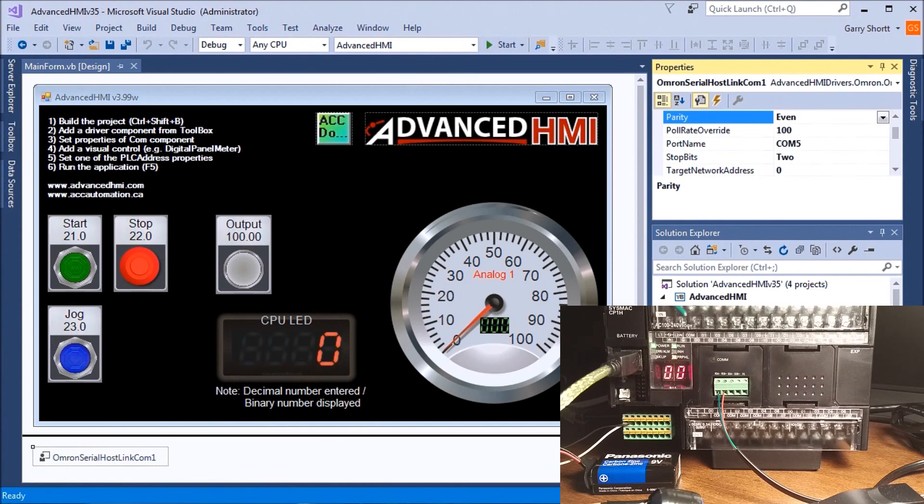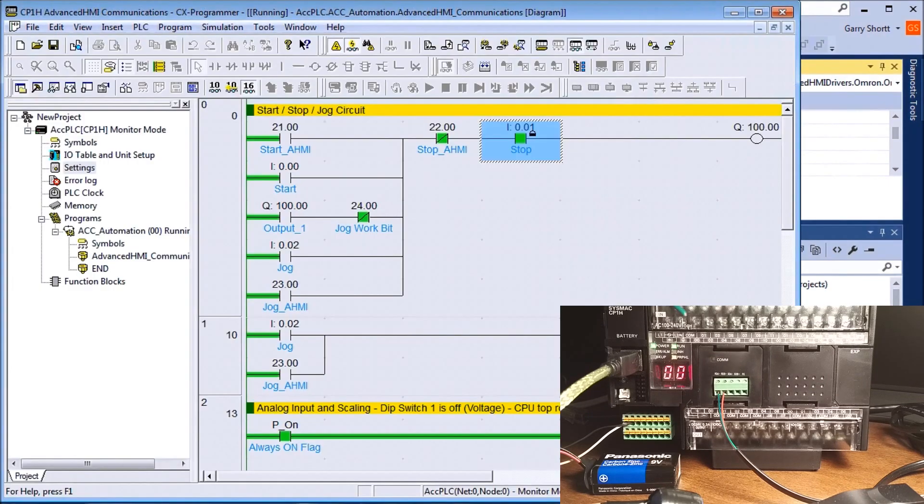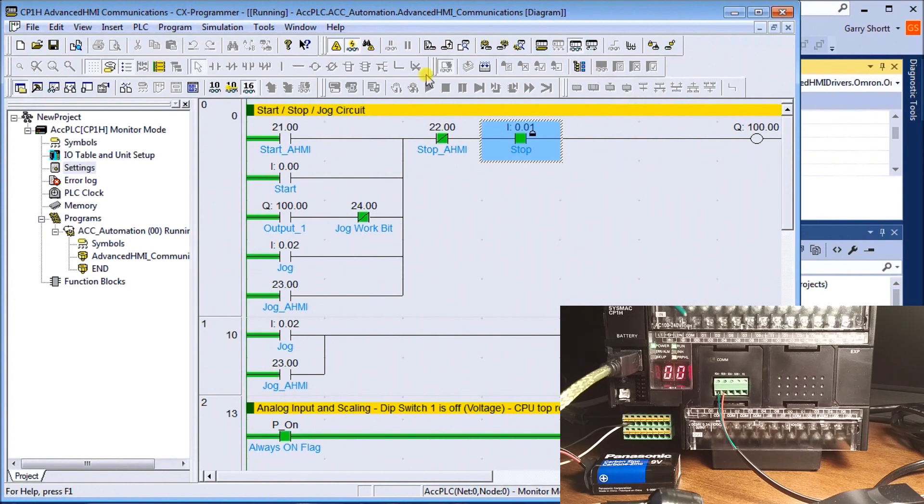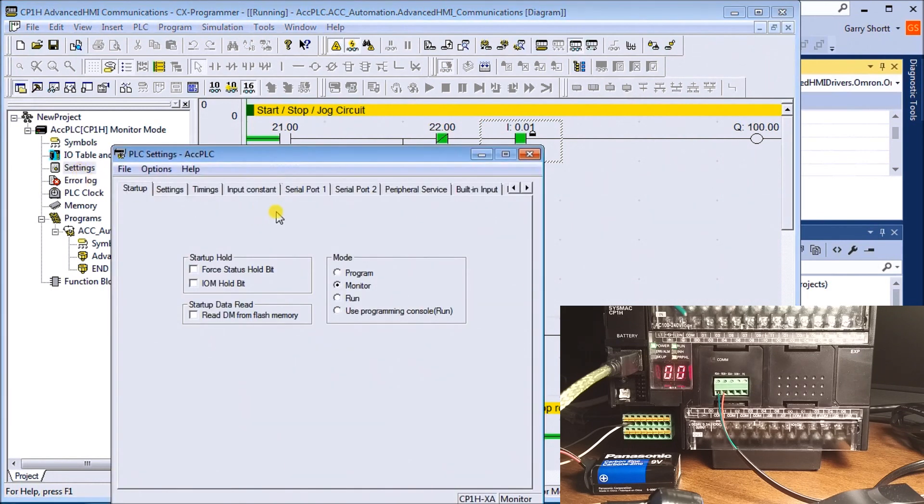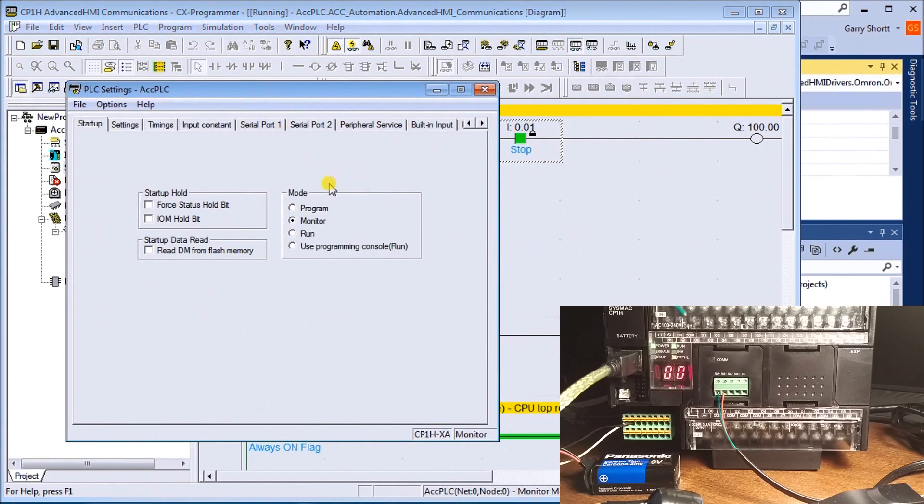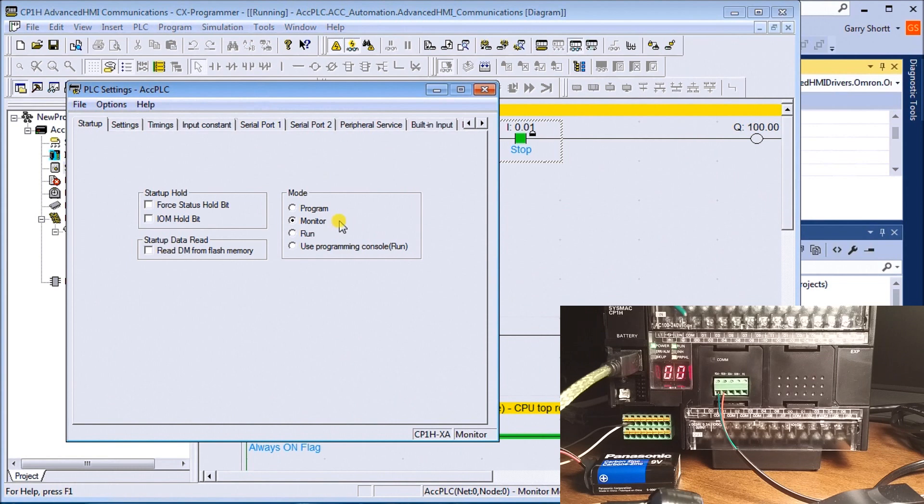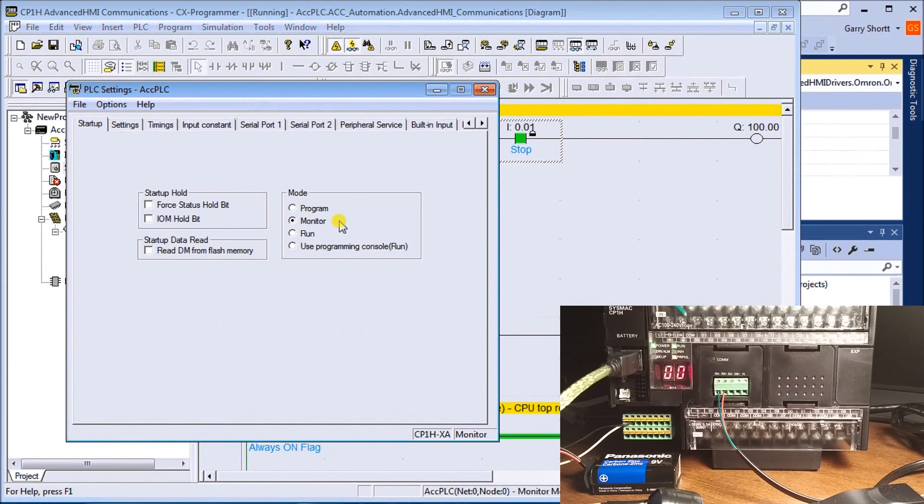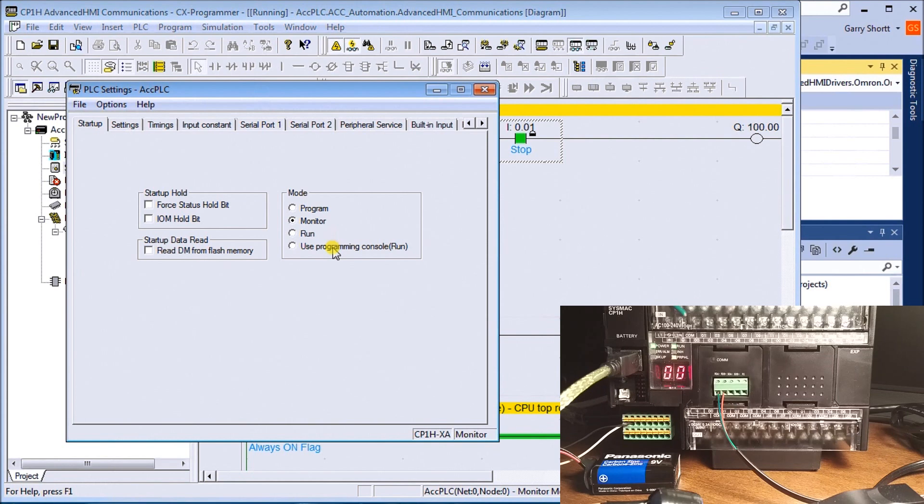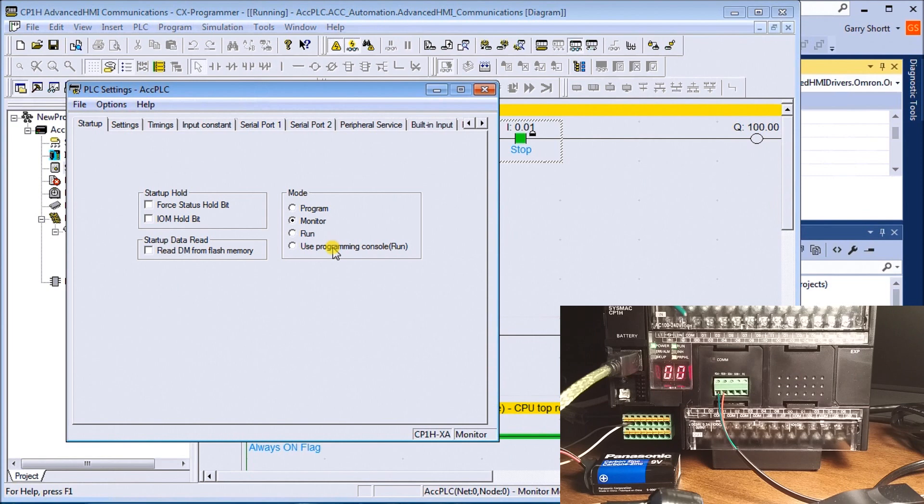In CX Programmer, the first thing is to ensure that under Settings, under Startup, we select mode Monitor. That's important because every time the PLC powers up, it will go into a default mode, typically Run mode. In Run mode, communications through the COM port will not change variables in the PLC.